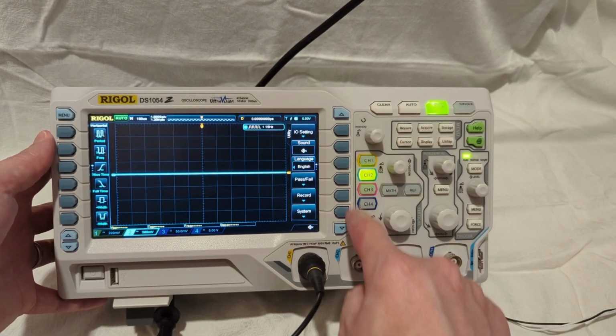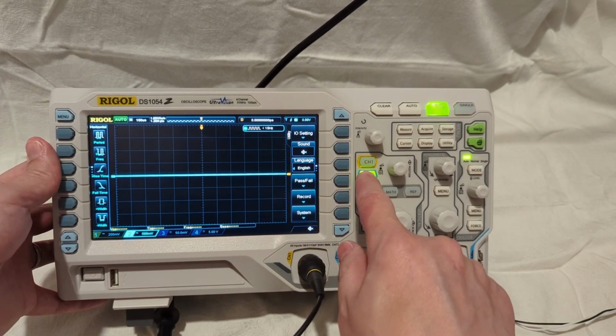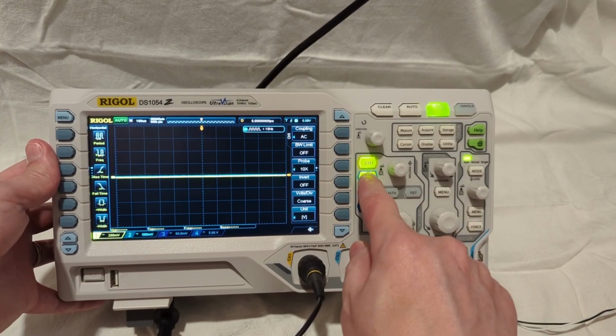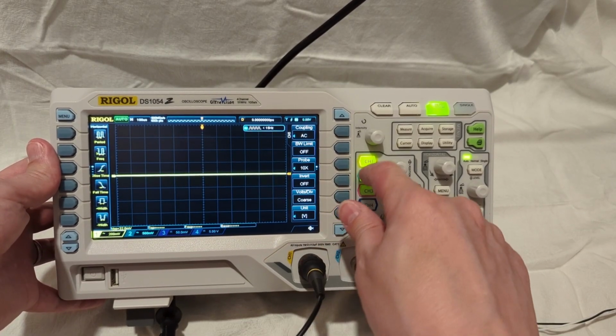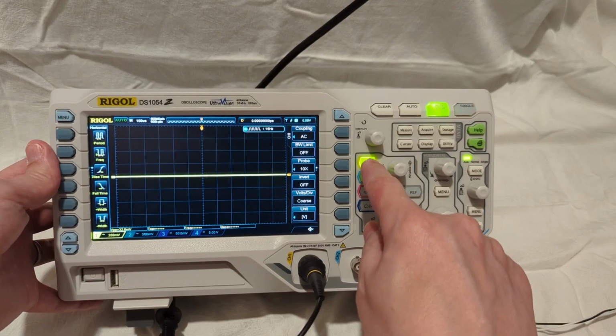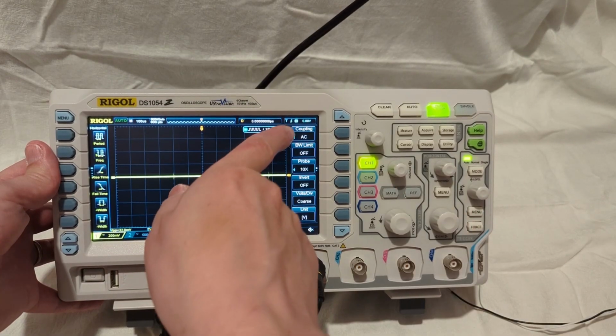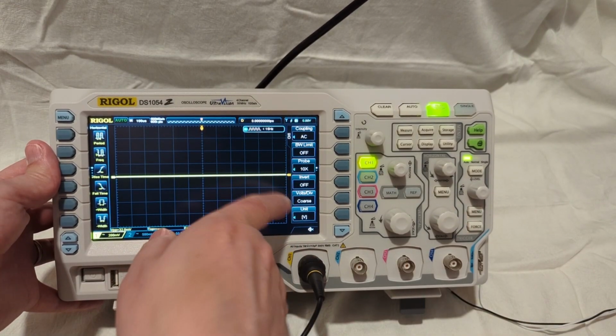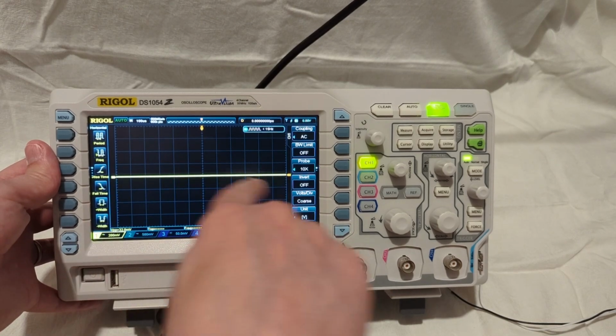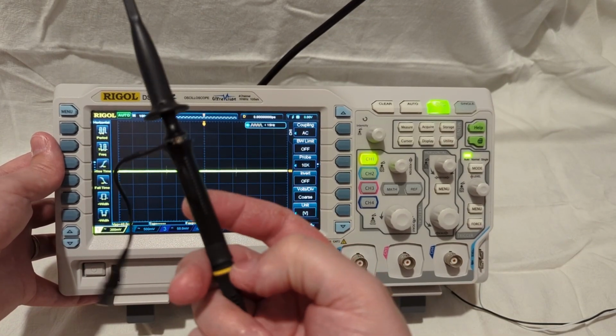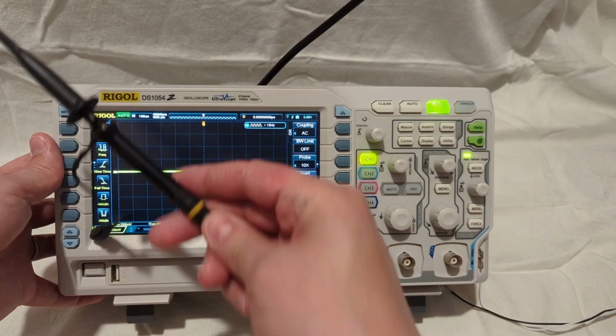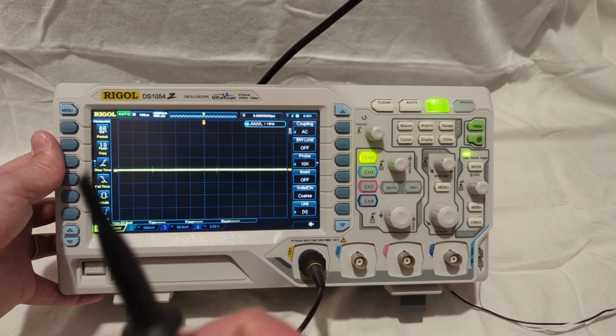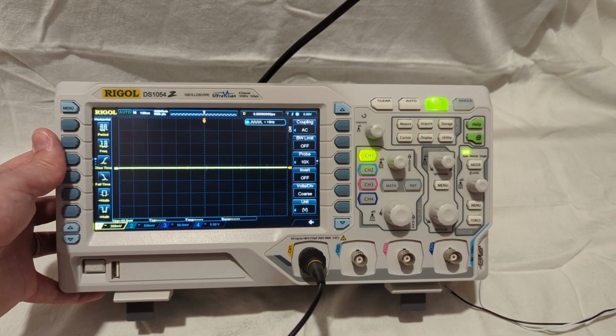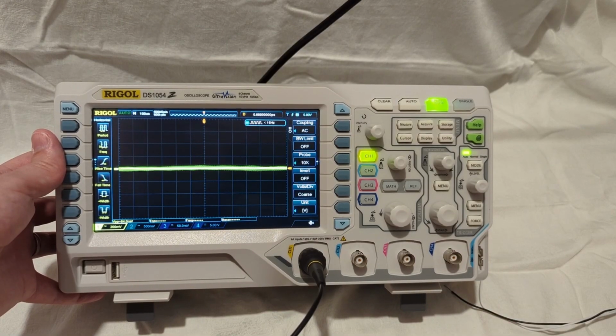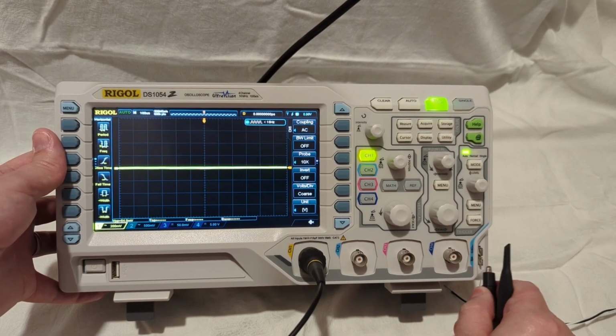You've got your channels right here. This is the vertical control. So if we're looking at channel 1, which is the one I have connected right now, I'm going to turn off channel 2 here. With channel 1, these are all the menu items for channel 1. And that brings up my channel 1 signal, which is yellow. You can see that I've connected up the yellow plastic here so that it matches up whenever I'm measuring stuff. That's very handy. And whenever we measure a signal here, let's go ahead and hook up to our calibration signal.